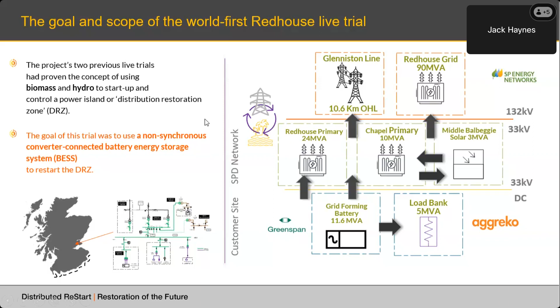The BESS performed excellently in terms of energization characteristics. So we've proved that the BESS is very effective at starting, maintaining and controlling power islands, with the added support of a diesel generator or not, that it can energize both distribution and transmission assets, both transformers and lines, and is much more effective at doing so when utilizing a device called a point-on-wave relay, which I'll provide some more detail on in a subsequent slide.